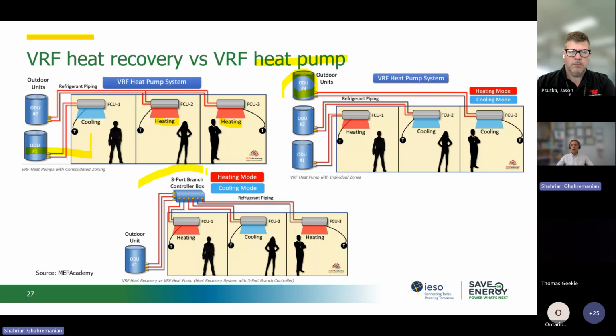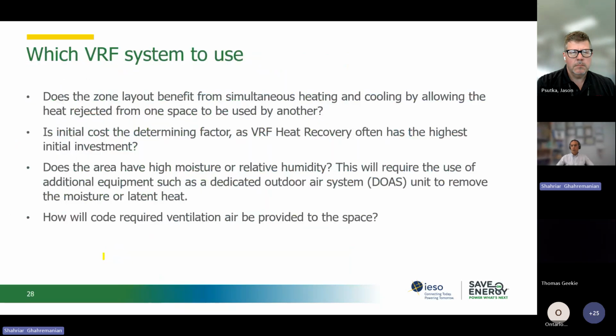But the good thing is that now we have a technology advancement, and we have a branch controller box, which means that we need to install only one outdoor unit, and this outdoor unit is connected to this branch controller box. And then each of zones one, two, and three can decide what they want. Do they want heating or cooling? They can basically switch whenever they want actually, and the outdoor unit connected to that controller box can manage that actually. So that's the beauty of heat recovery. This system is called VRF heat recovery heat pumps actually. So this is a good one to be considered for our buildings.